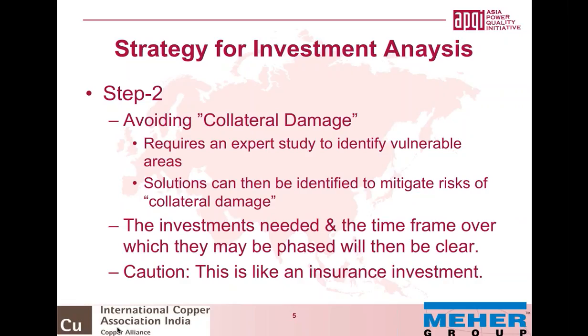This expert study need not be from a power quality expert, it could be from an equipment expert. Let's say in a hospital I am installing a very sophisticated CT scan machine, most advanced etc. It may require that the voltage, frequency, neutral to earth voltage, and total harmonic distortion of the supply be maintained within a certain level. It's important that the user of that equipment understands this from an expert and ensures that his electrical engineering design of the network is made in such a way that those parameters can be achieved.